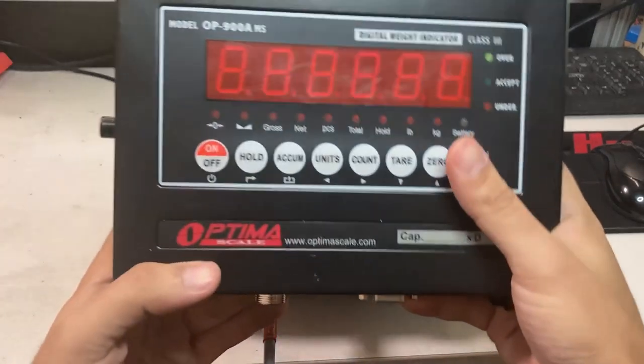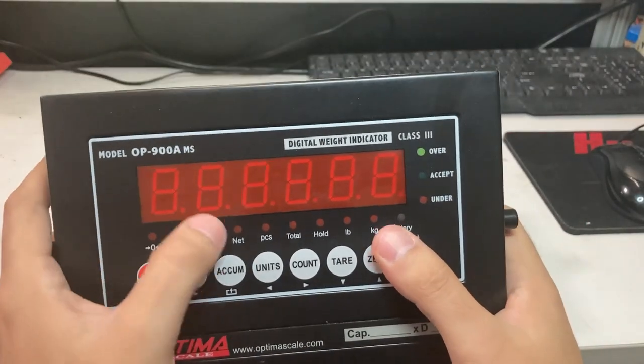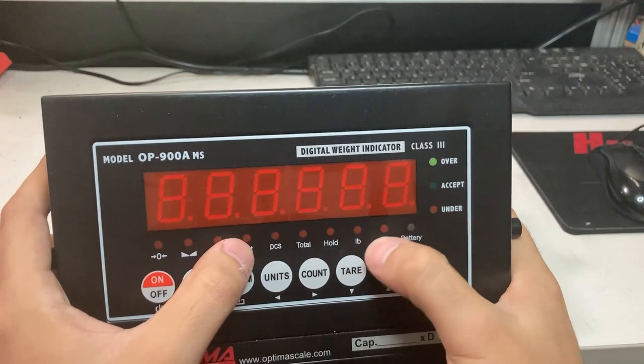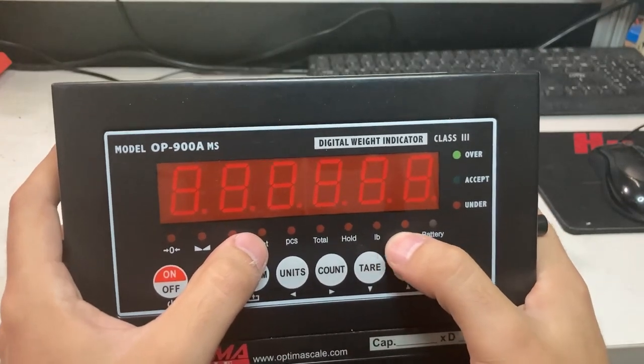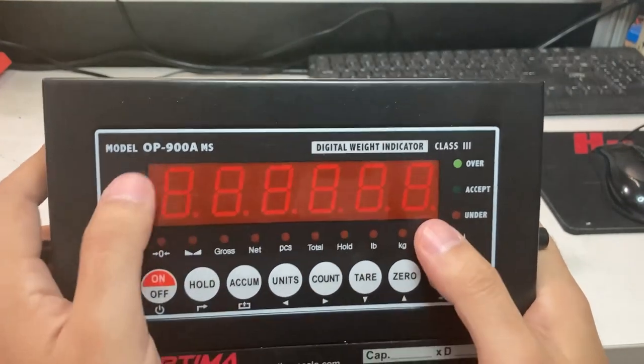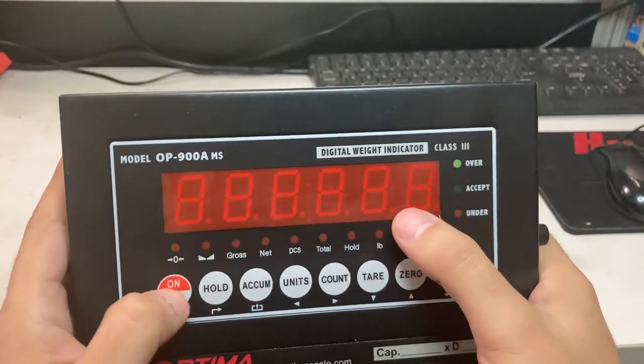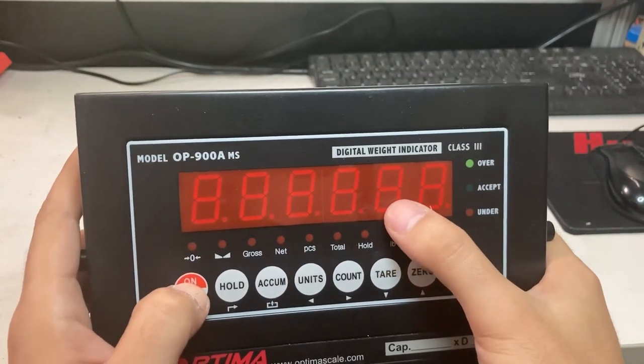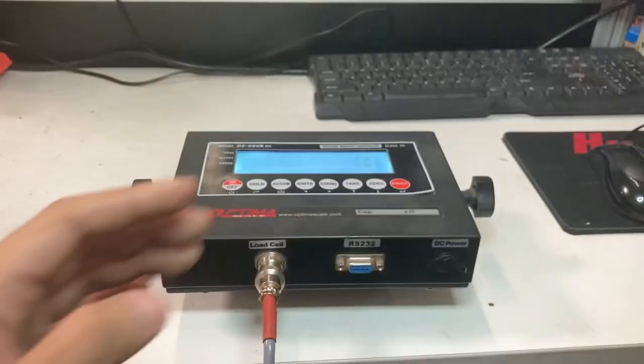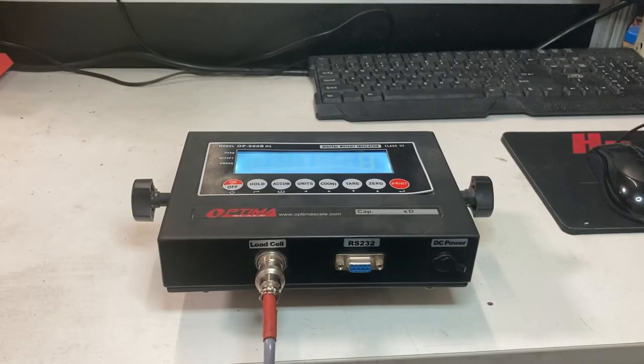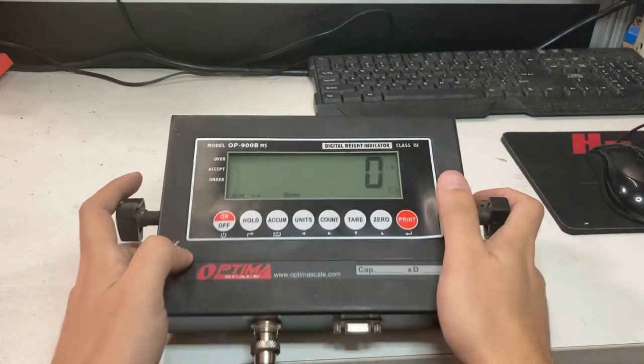If you have the OP900A, these only do pounds and kilograms, and that's it. So you will not be able to enable ounces or grams in the 900A. You'll tell because when you turn it on, the numbers are red and black, while this one is white and black. So I want to specify that to make sure it is the LCD model when you're enabling grams and ounces.